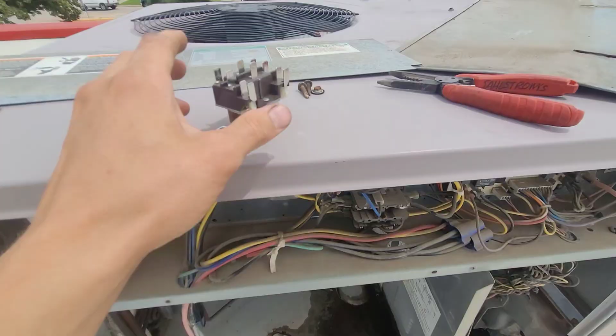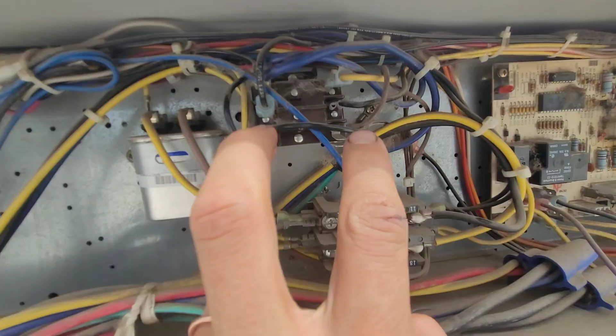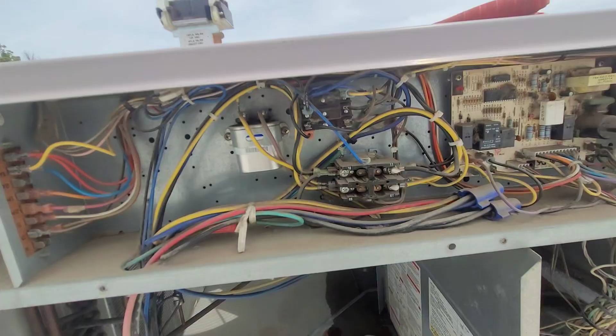Okay, this is super weird. I think we have a case of transformers fighting each other. But I arrived and for some reason the blower was not running. Thought it was maybe this relay, so I was gonna just change out the relay because it wasn't snapping in. But then I realized there wasn't actually any voltage to where the coil leads are on this black and brown wire. If there's no voltage present, then it's not gonna snap in.